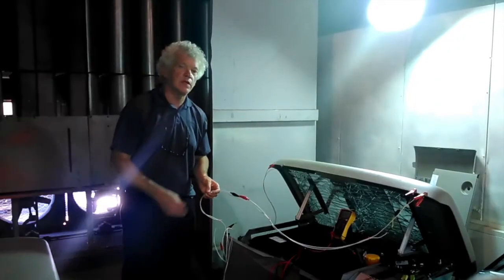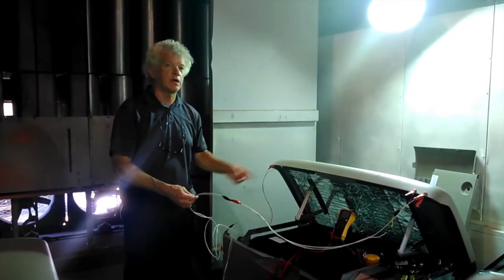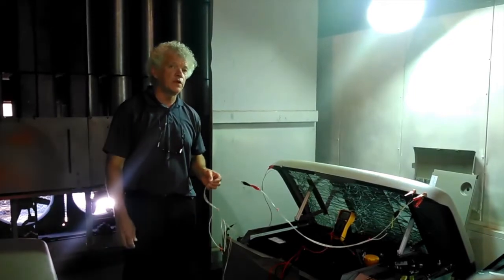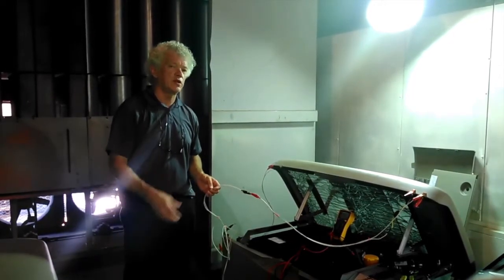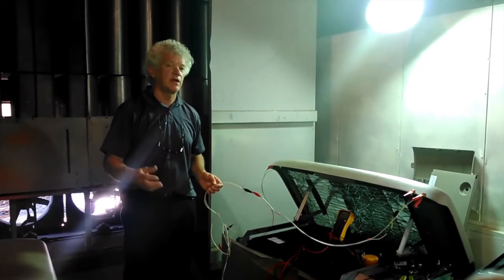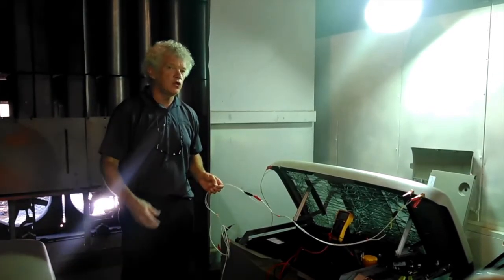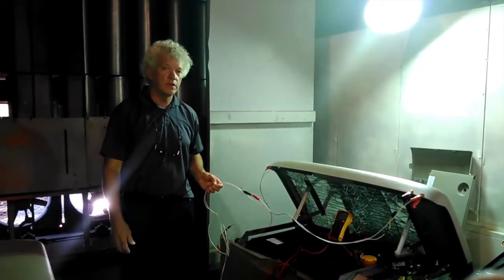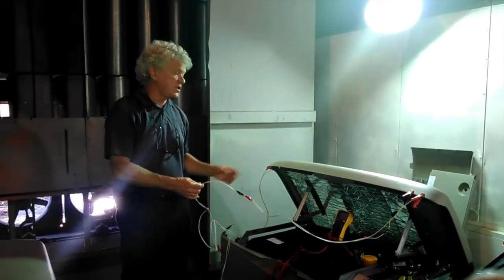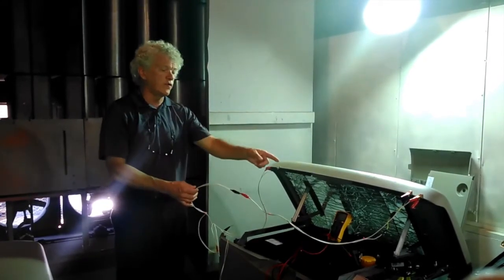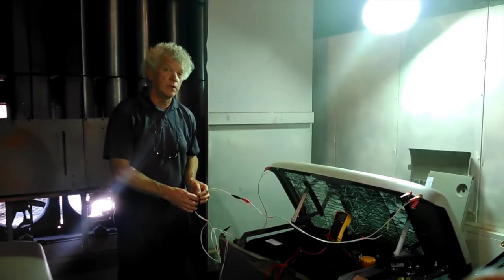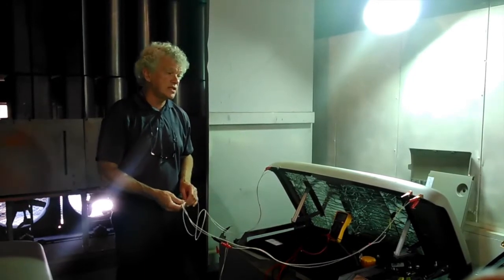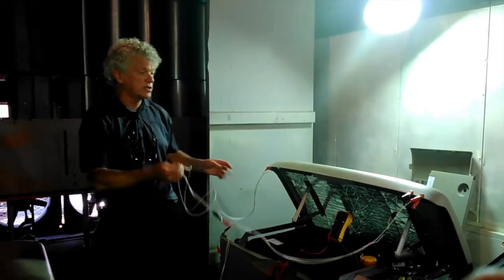This video is to demonstrate doing a separate excitation on a 20 RESA. The reason for doing a separate excitation is if you're running a generator, you're not developing desired output voltage, you're getting a locked rotor fault. You need to determine if it's the alternator is an issue or do you have a voltage regulator in the controller issue.